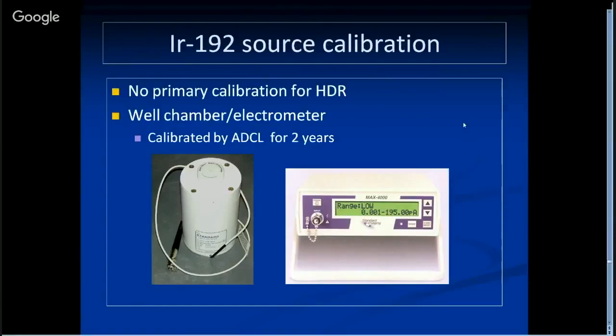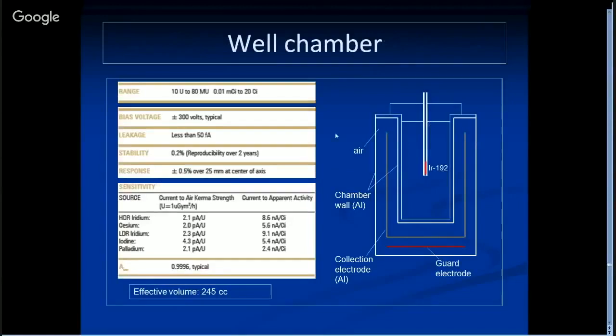For source calibration, you need a well chamber and electrometer, both calibrated by the ADCL, valid for 2 years. This is the schematic of a well chamber - you have a chamber, the air, a collection electrode which is aluminum, and an aluminum wall. You put the source in and get the reading.